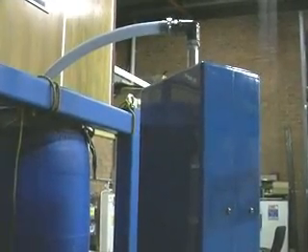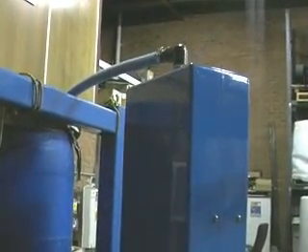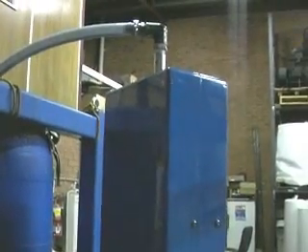There we go — it slows down. Okay, we've now done the clean. It still leaves a small amount in there because we can't go right close to the bowl — pushing it in as hard as I can. So that's basically 5mm remaining. You can see where the mud is. Just one clean — it's removed about 5 litres of solids, and the rest is mostly liquid.